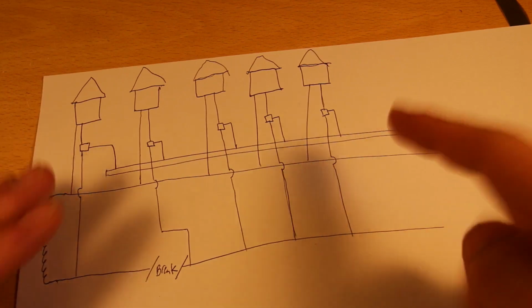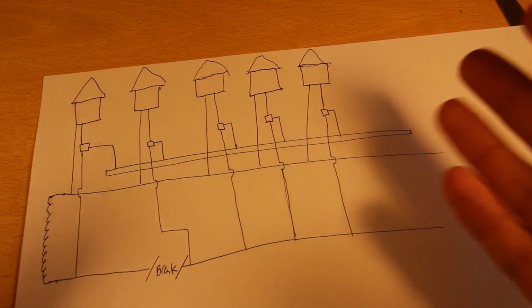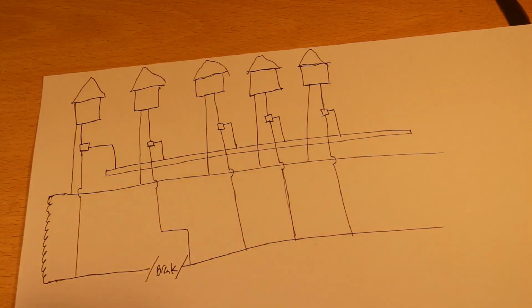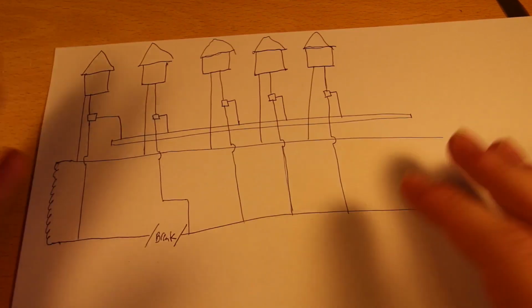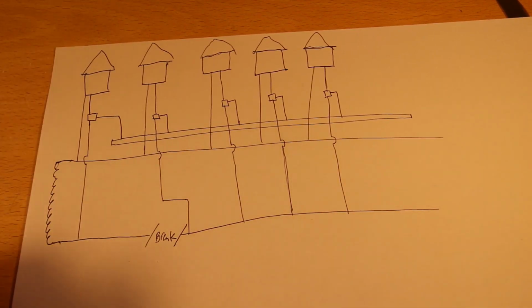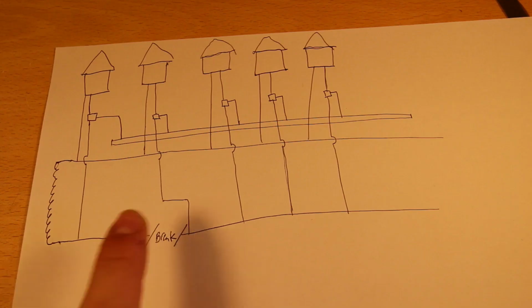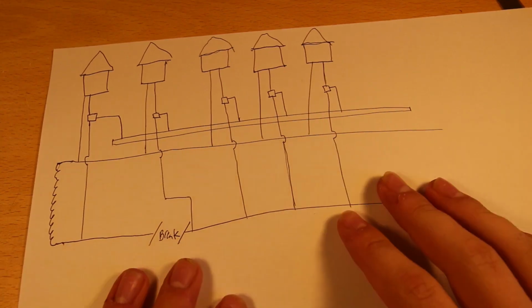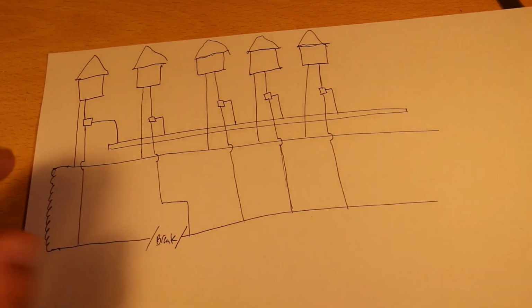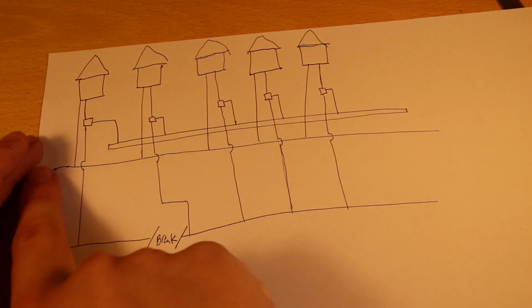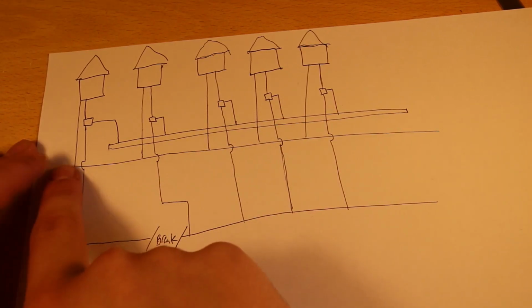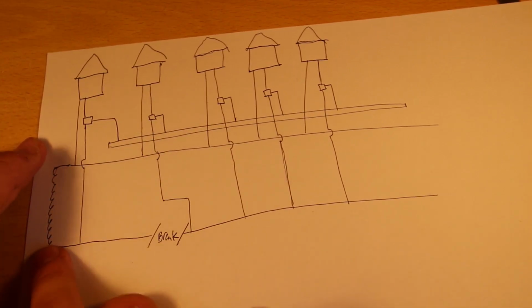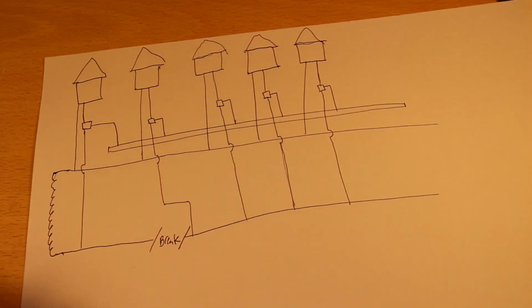And this here is a gas main or a water main or some utility pipe. What has happened in this place though is, unfortunately, the PEN conductor has broken partway along the street here. Now, what happens? So the load current goes in the first house, out the live, up through the load, back down the neutral, back to the substation. That's fine, that's working as it's supposed to.